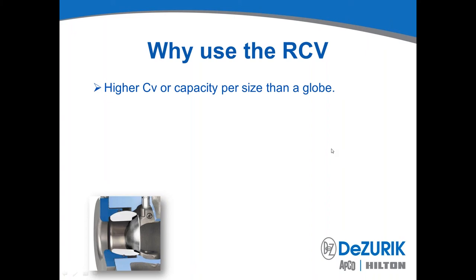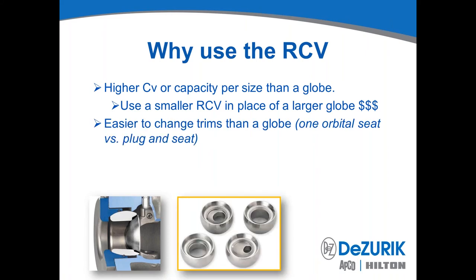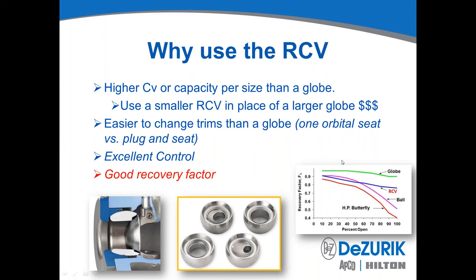So, why use the RCV in review? It has a higher CV or capacity per valve size than a globe, which could be a significant cost savings — you can use a smaller RCV in place of a larger globe, and that is where the dollar savings can be realized. Easier to change trims than a globe valve — one orbital seat versus having to replace a plug and seat. From a maintenance standpoint it is very easy to do. It has excellent control, and it has a very good recovery factor.